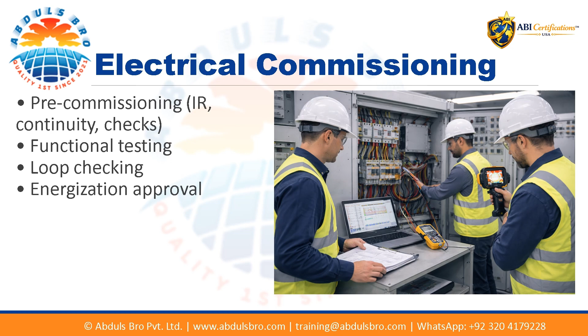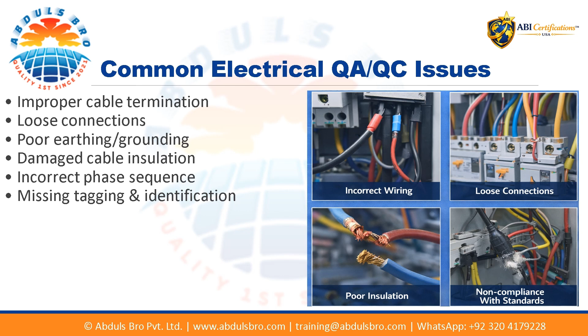Common electrical QAQC issues: in real projects, many issues occur in electrical installations. Improper cable termination can lead to overheating and failure. Loose connections are one of the most common causes of faults. Poor earthing affects safety and system performance. Damaged insulation can cause short circuits. Incorrect phase sequence can damage motors. Missing tagging and identification create confusion during operation and maintenance. The Certified QAQC Engineer CQE Electrical ensures that all these issues are identified and controlled before system handover.